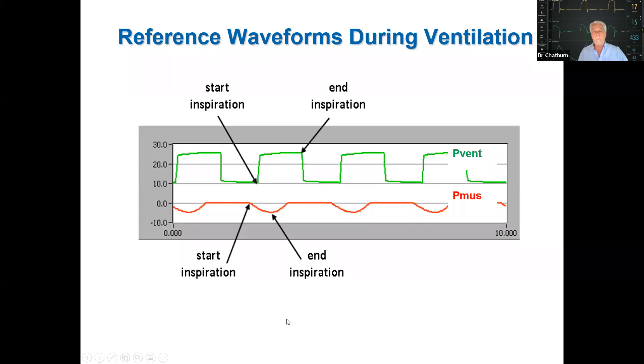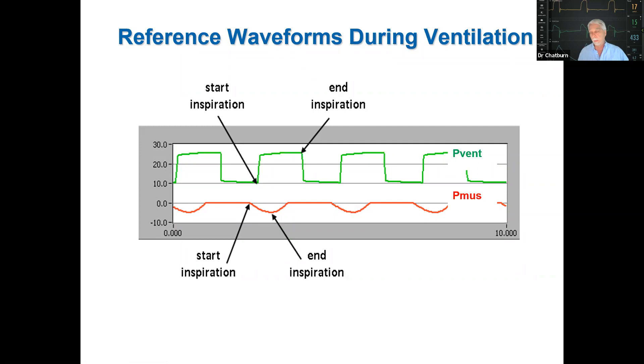The reference signal in all forms of synchrony evaluation has to be what the patient is doing — ideally muscle pressure (P_mus). Muscle pressure has actually been measured at the bedside and is embedded in proportional assist ventilation, though we rarely see it directly displayed on ventilators. A surrogate for muscle pressure might be esophageal pressure. This is our reference signal. The signal that's supposed to respond in synchrony is the airway pressure waveform — P_vent. You want P_vent and P_mus to be in synchrony.